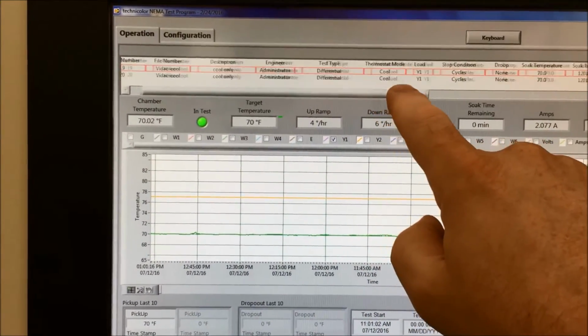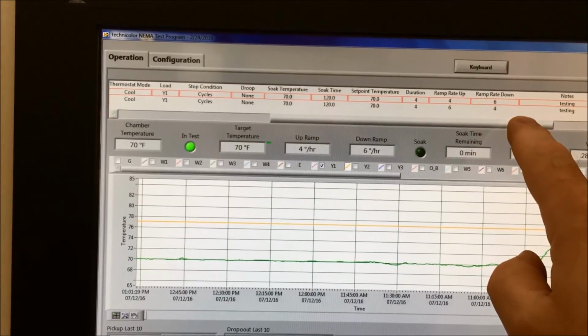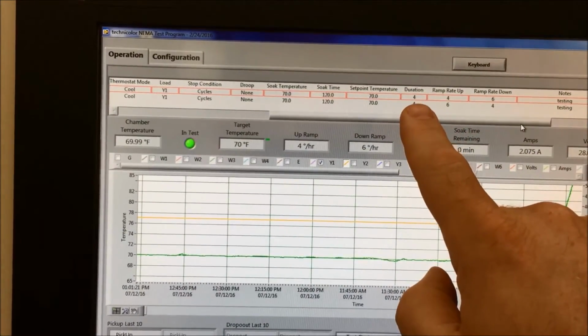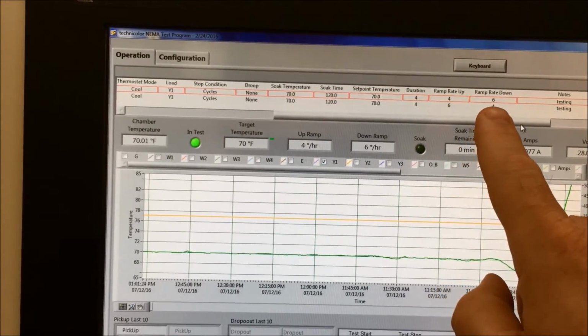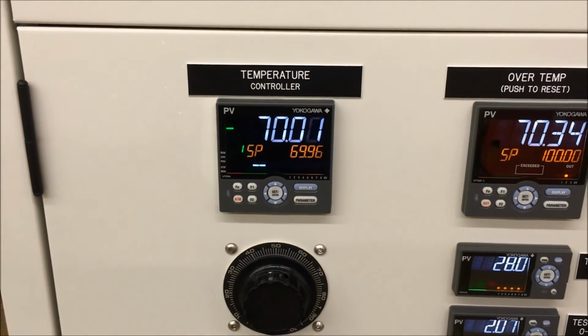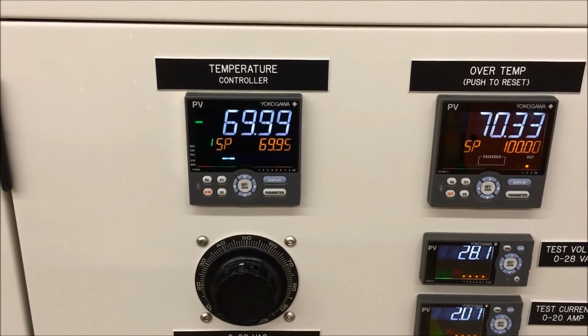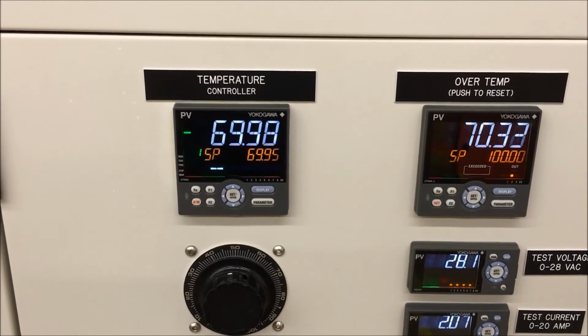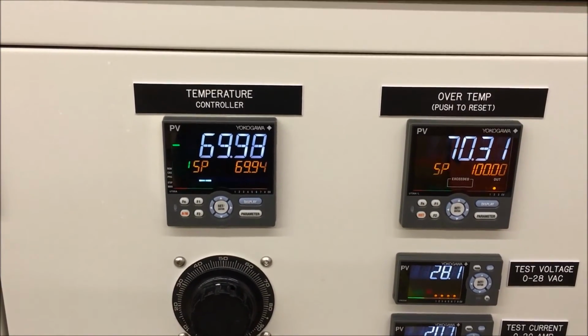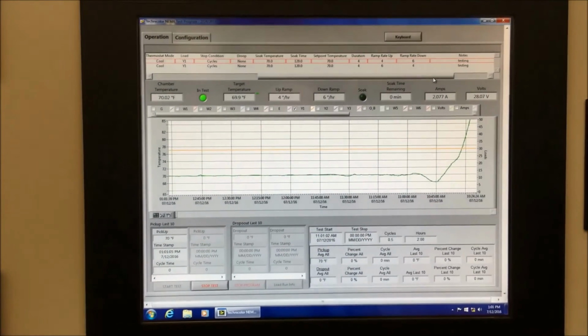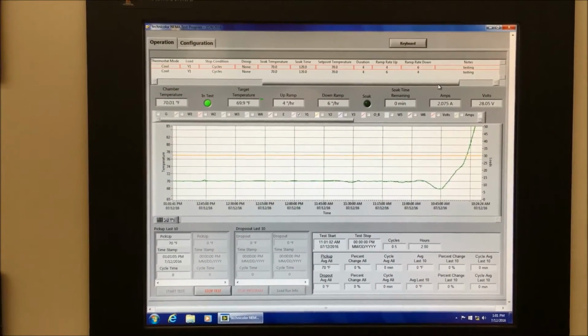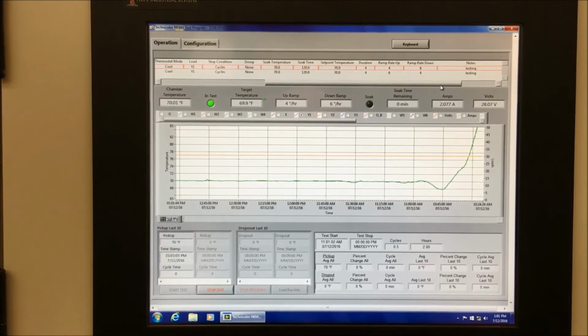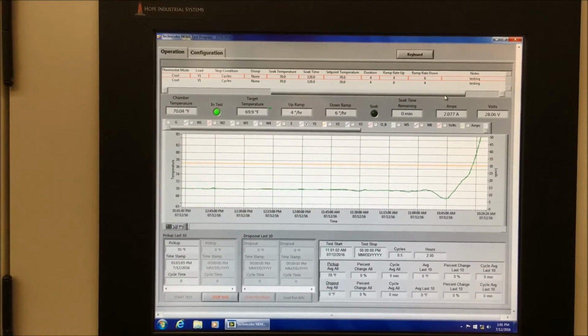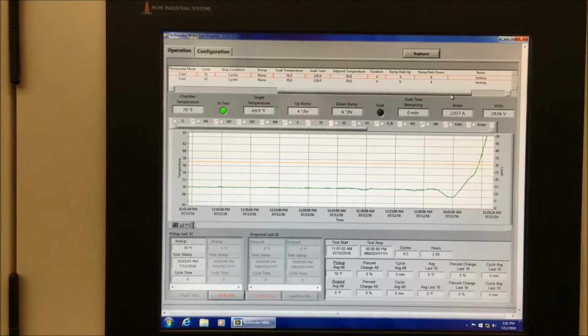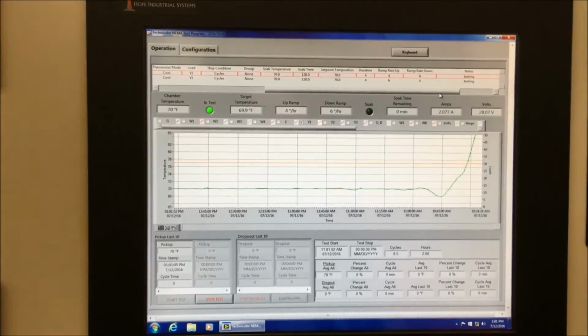Let's scroll over using the touch screen. And our first test is for a duration of 4 cycles, 4 degrees up, 6 degrees down per hour. So if we look at our temperature controller, it is now dropping at 6 degrees per hour. If we come back and visit our test, you'll be able to see if the thermostat operates correctly, a triangle wave of sorts that'll show the on and off position of where the thermostat turns on.